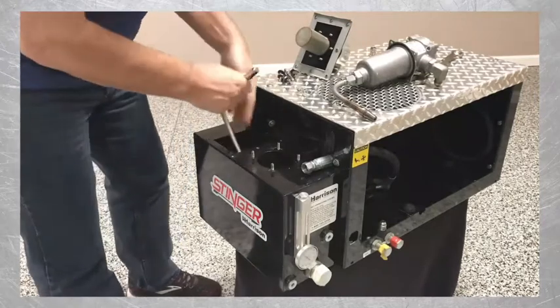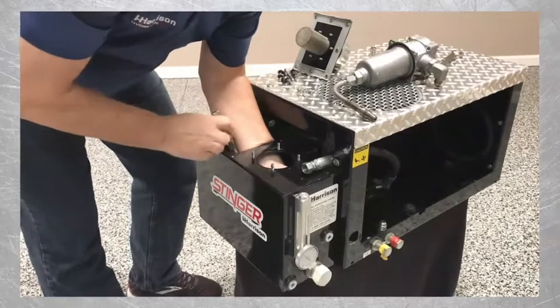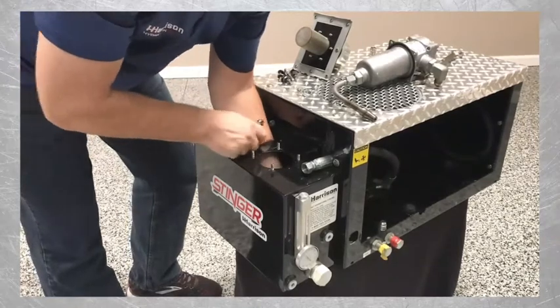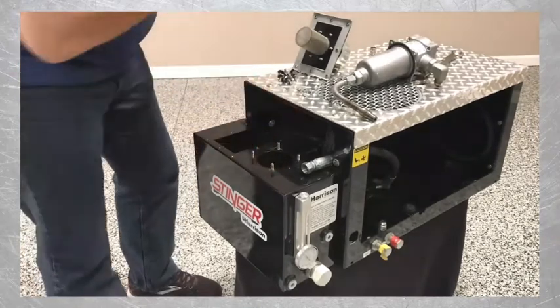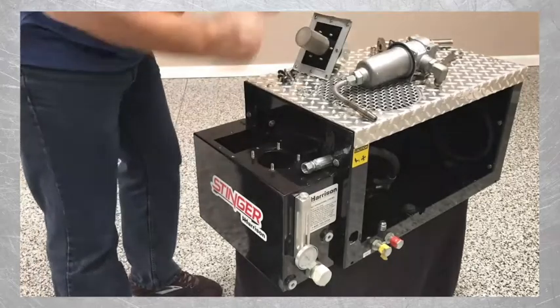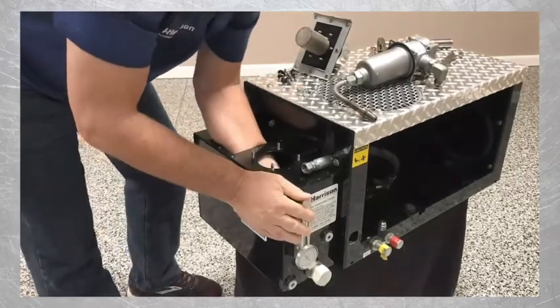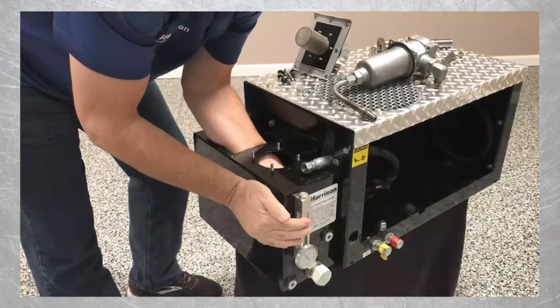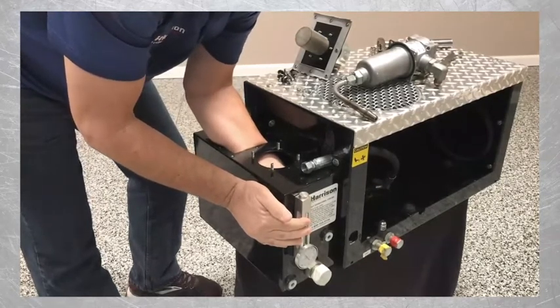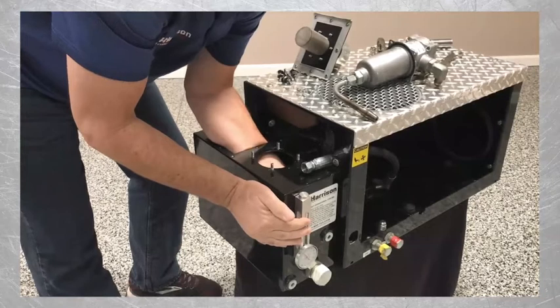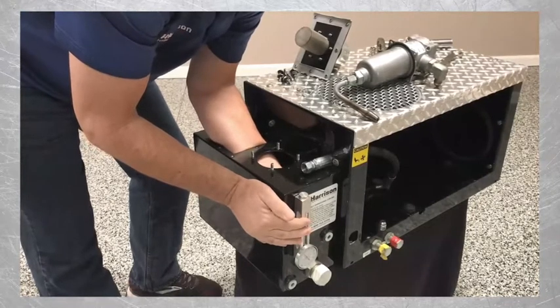Now you can use your 3/4 inch deep socket with the 6-inch extension to loosen the 2 nuts holding the level gauge to the reservoir. These nuts won't be very tight, so once you break them loose, they'll spin off very easily. But the threaded posts are quite long, so it'll take a bit of time to get those off.